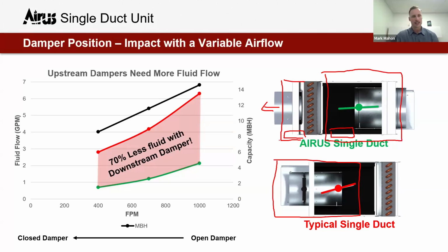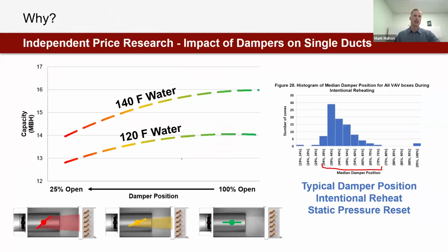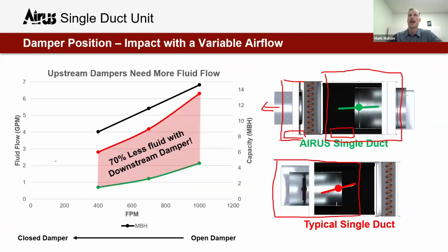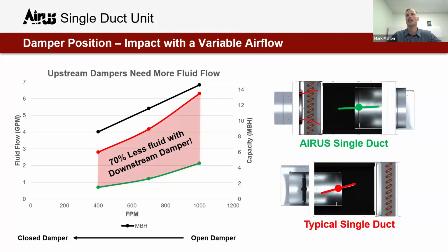A question from Heidi, why does moving the damper mean less fluid flow? And so the importance here, and I'll go back here to answer Heidi's question, as the damper gets more shut in a traditional single duct, it's essentially casting a larger shadow on the heat exchanger, and we're going to see airflow hit the top and hit the bottom of the coil. When we move the damper downstream, we're going to get that main mass, and I'm going to remove some of the ink here, the main mass of air is going to go right through the middle of the coil. It actually spreads a little bit as it travels through. And this is true independent of damper position. And that's the big influence there. More effective usage of the coil surface area, and therefore a greater heat transfer, which means less fluid flow requirement.